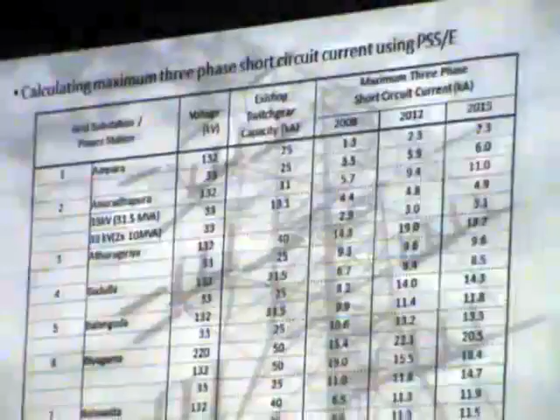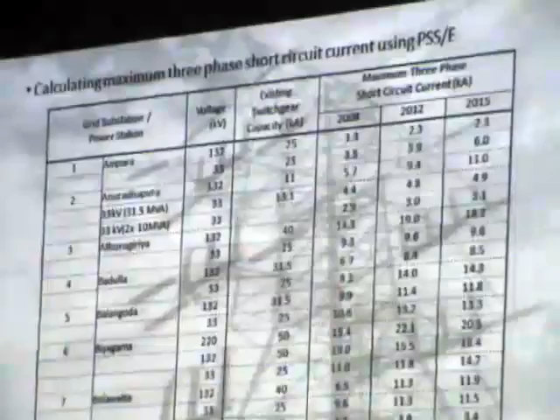So this is some extract from our maximum three-phase short circuit current. You can see here that Anuradhapura, this is old Anuradhapura, in 2015 it reached the switchgear capacity.